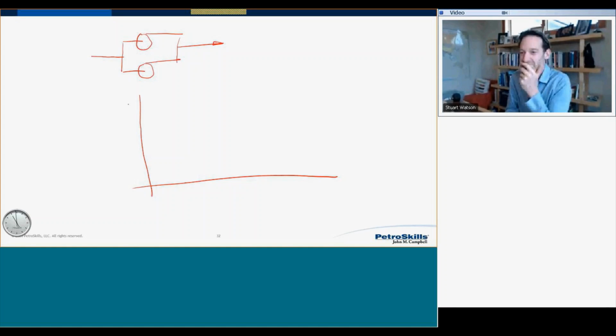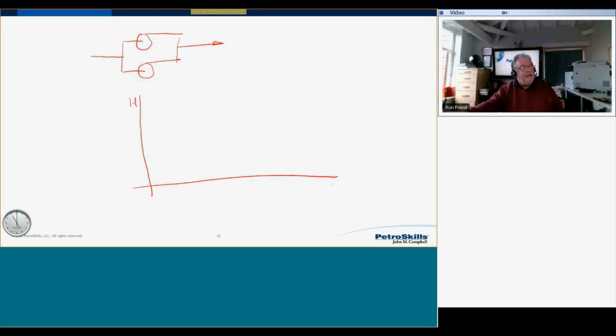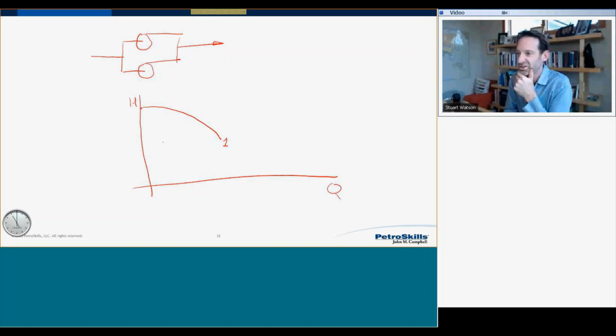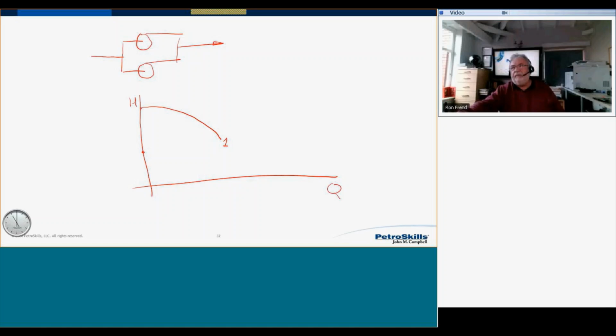I do. Okay, so we've got head and flow. Let's think about our system curve first. Actually, no, let's think about the pump curve. If this is the pump curve for one pump, and the system curve, what sort of process was this? Assume that it's a medium friction system curve. Okay, so let's say our static head starts about here, and then we add the friction to this, and we end up there somewhere. That's our operating point. That looks good.